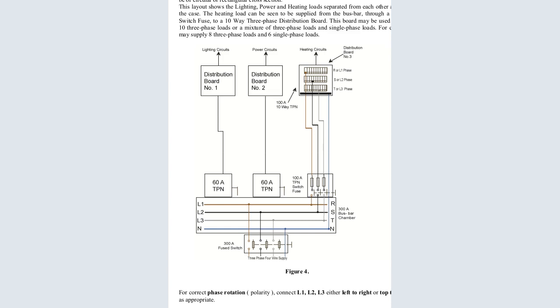This is what is coming into the meter board before it gets into the distribution board. We normally have three fuses at the meter board. This is the first fuse for the first live line, the second fuse for the next line, the third fuse for the third line. And then this is the neutral. You can see the neutral is tapped from the pole. This is the neutral that is normally supplied by Kenya Power. We say the neutral is given by the supplier, Kenya Power.